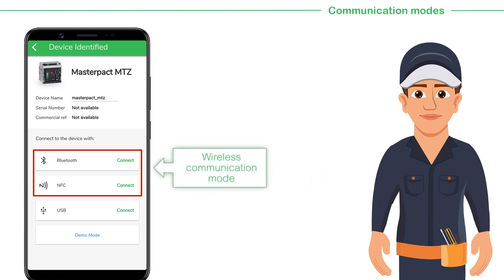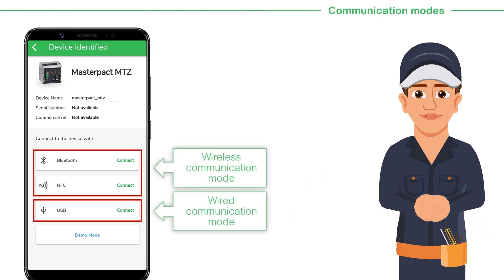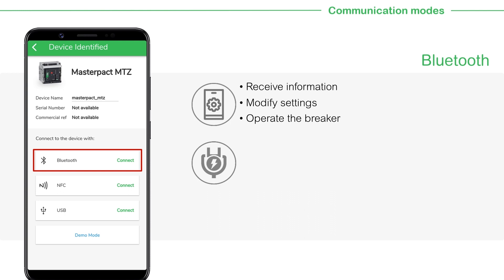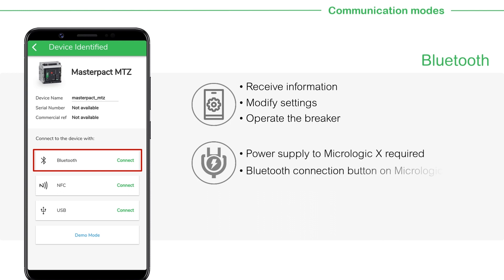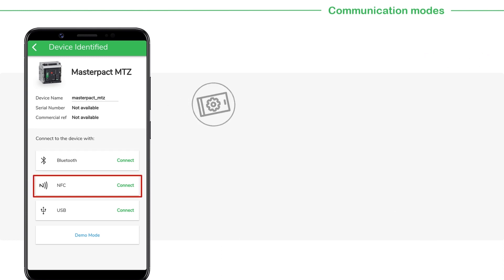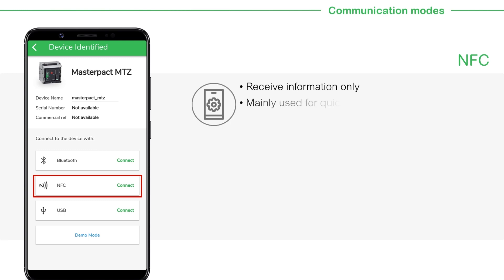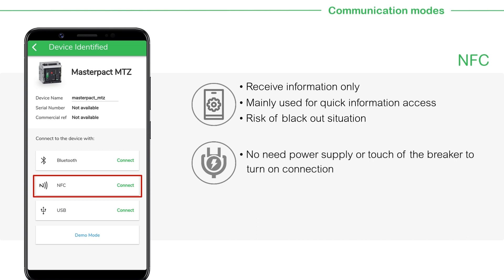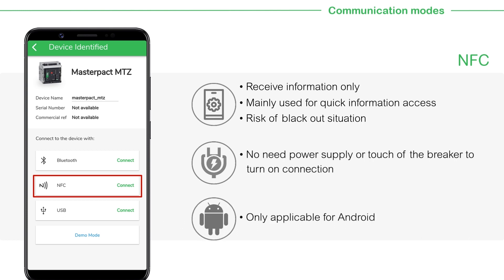There are two wireless communication modes and one wired communication mode available for connecting the device. Using the Bluetooth mode, you can receive information, modify settings and operate the breaker. The power supply to MicroLogic X and pressing the Bluetooth connection button on MicroLogic X are necessary. This communication mode is applicable on both Android and iOS platforms. Using the NFC mode, you can receive information only. It is mainly used for quick information access, blackout situations or other situations where potential risk to touch the breaker exists. No power supply or touch of the breaker is required to turn on the connection. This mode is only applicable on Android phones.